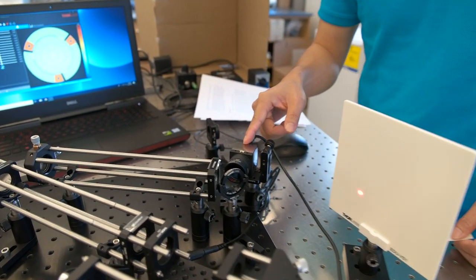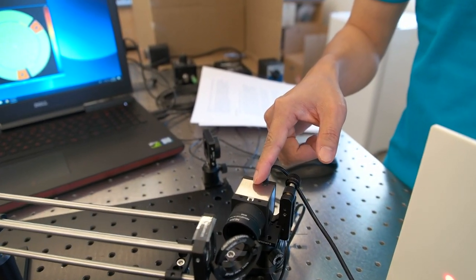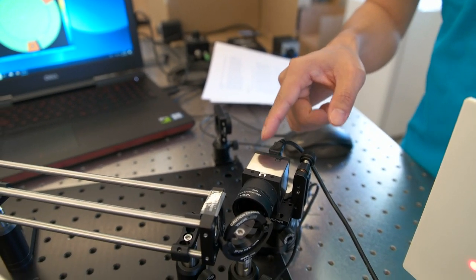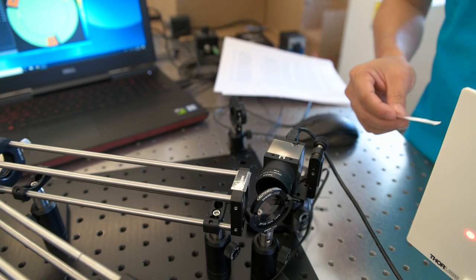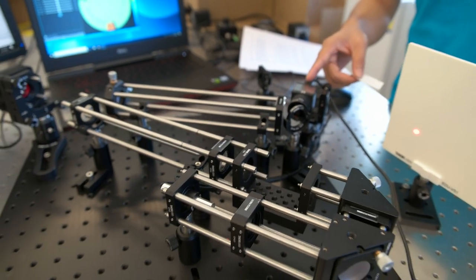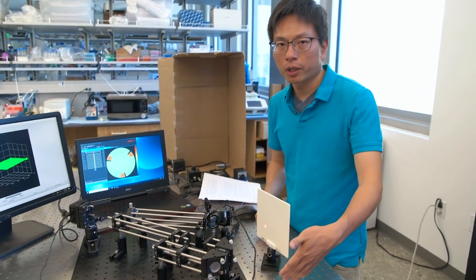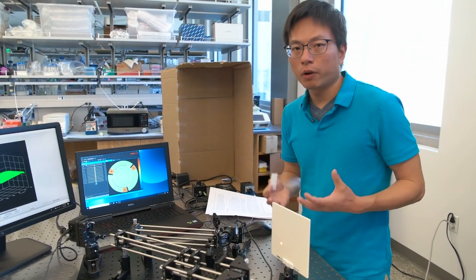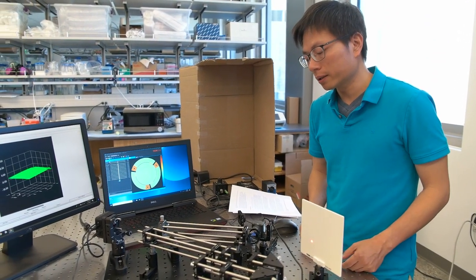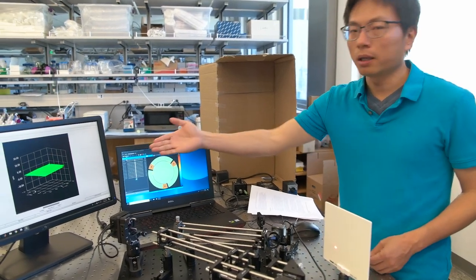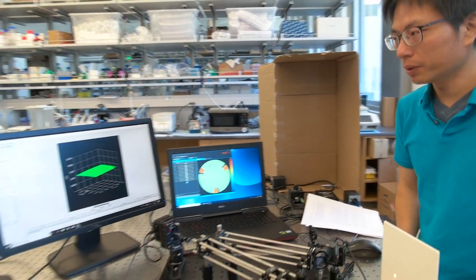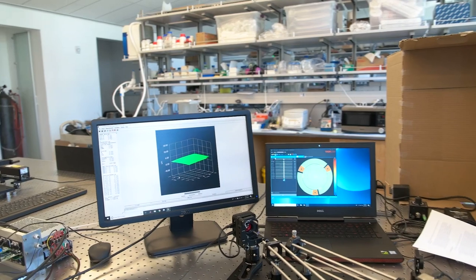Inside the wavefront sensor, there is a micro-lens array and a camera. The detected signal from the camera is sent to a computer under the optical table so that the shape of the wavefront can be calculated and displayed on the computer monitor.